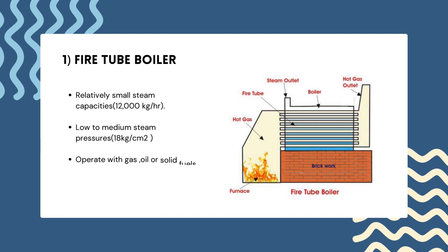The first type is the fire tube boiler, defined as a boiler consisting of a sealed container filled with water and a series of tubes running through it. The tubes carry hot gases from fire, usually fueled by coal, oil or gas, that heat the water and generate steam. Fire tube boilers can generally produce low to medium pressure steam up to 17.5 bar and low to medium capacity up to 9 metric tons per hour, with a small steam capacity of 12,000 kg per hour and steam pressure of 18 kg per centimeter square.